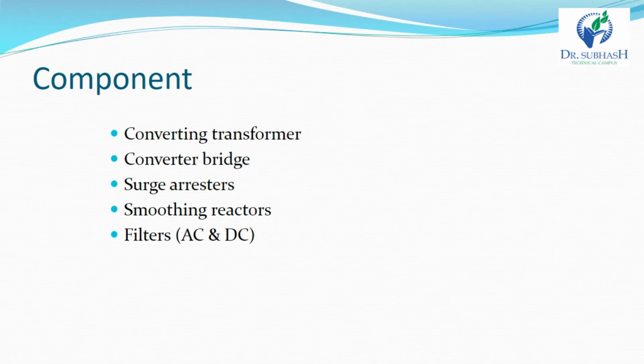The AC side windings of the two three-phase transformers are connected in star with their neutral grounded. The valve side transformer winding is designed to withstand alternating voltage stress and direct voltage stress from the valve bridge. There is an increase in eddy current losses due to harmonic currents. The magnetization in the core of the converter transformer is because of the following reason: the alternating voltage from the AC network contains the fundamental and several harmonics, and the direct voltage from the valve side terminal also has some harmonics.